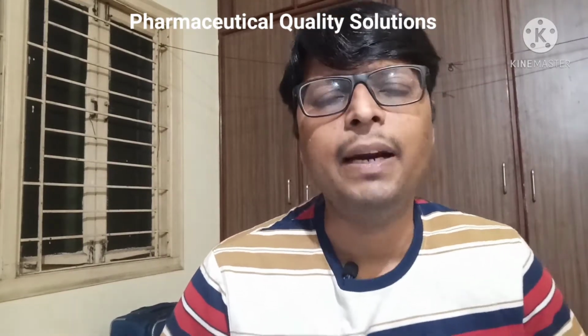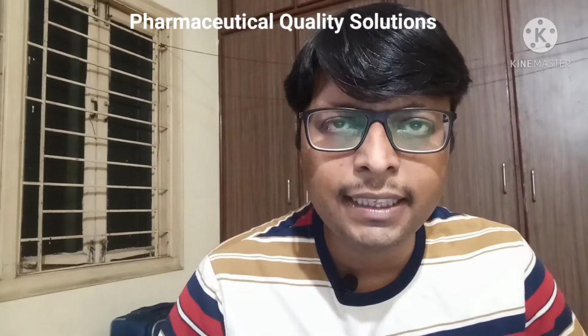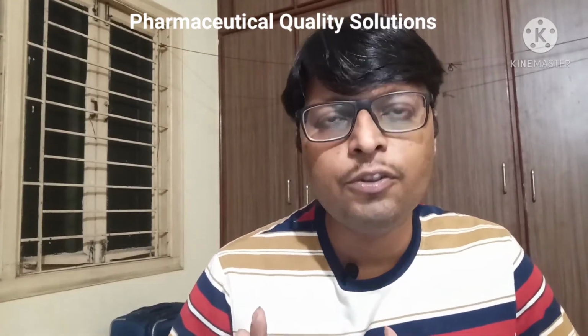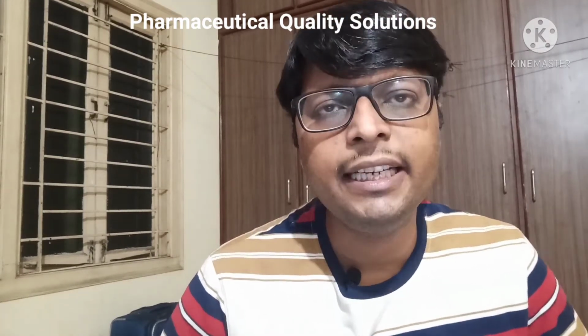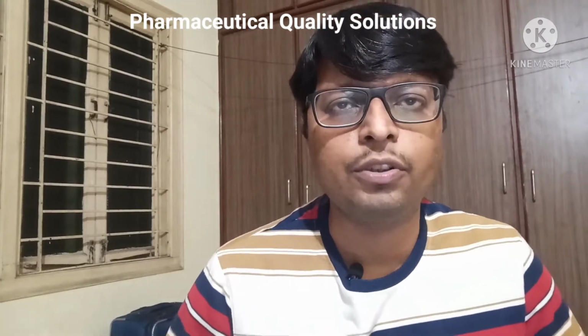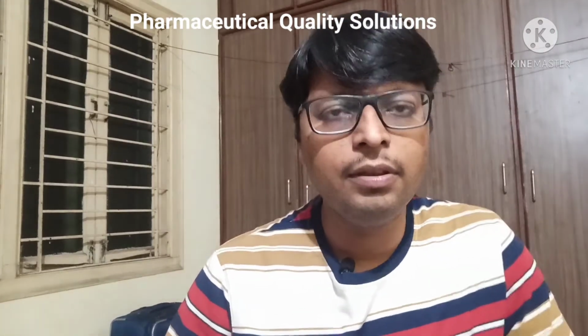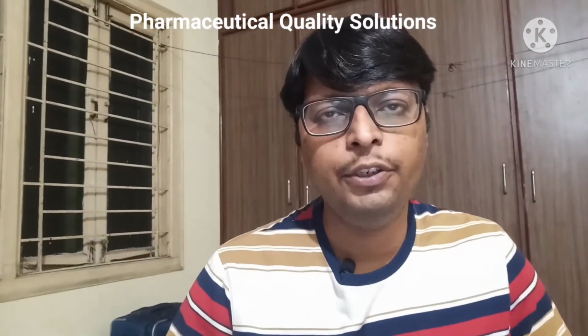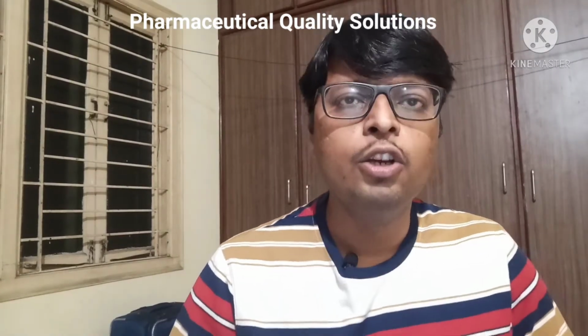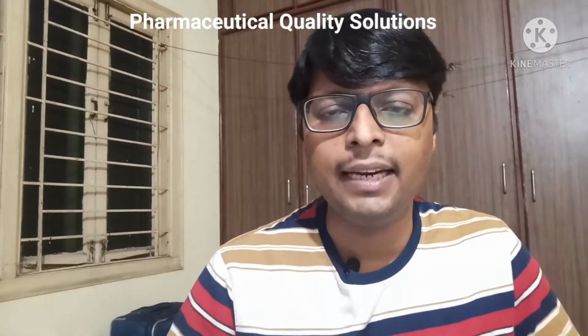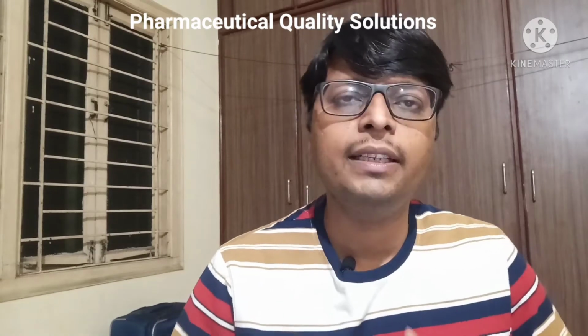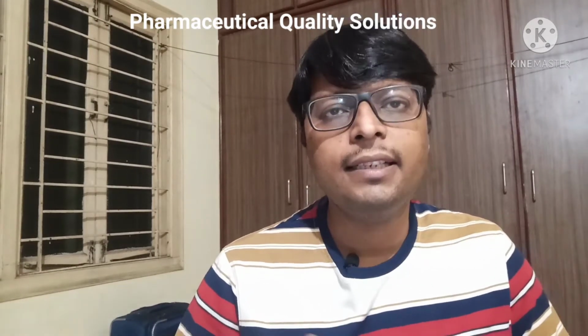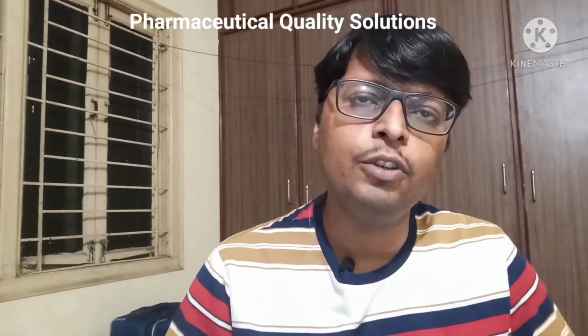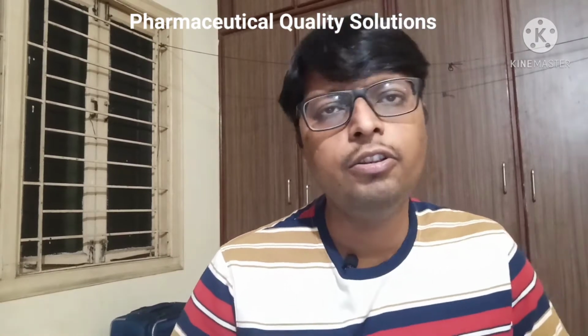This is the final part, performance qualification. Performance qualification is the fitness of that analytical equipment or instrument; you are checking its actual intended use. That means, suppose you purchased the instrument for a particular analysis. You run a dummy analysis on that instrument and check the result criteria, whether it is meeting the system suitability criteria or not.